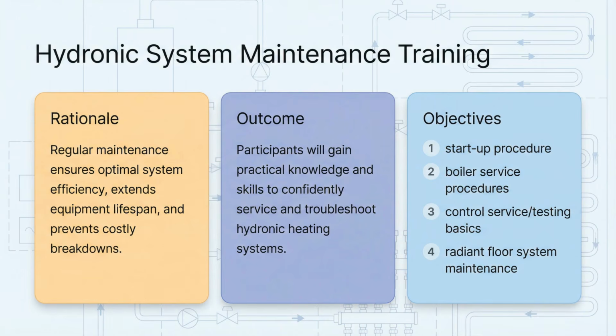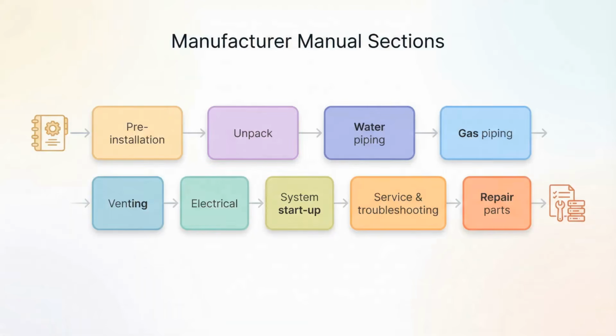The outcome is being able to install and service residential radiant floor hot water systems, and the objectives break into 4 areas: startup, boiler service, control service, and basic radiant system maintenance. A key idea is that boiler startup is manufacturer-specific. The manual typically walks through pre-installation inspection, unpacking, water piping, gas piping, venting, electrical, system startup, then service and troubleshooting, and finally repair parts. The safest approach is to treat that manual like the primary checklist.